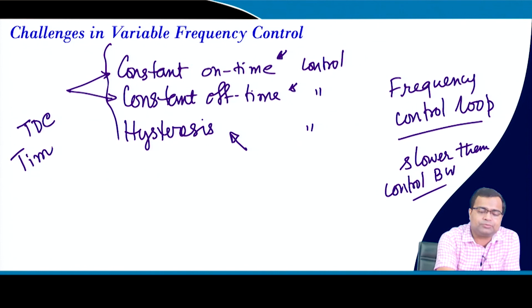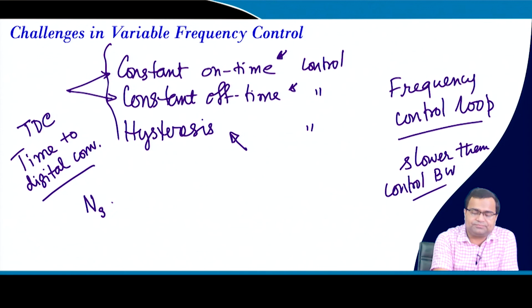And for these two techniques it is somewhat straightforward, because if you take a time to digital converter, you can get the instantaneous time period, create a feedback loop and compare it with the desired value. Let us say this is your instantaneous on time and this is your desired value. This is subtracted from the desired value, because these are all numbers, and then from the error you create a map, a function, that generates, in case of constant on time, the on time adaptation. That means it slowly adjusts the on time in order to achieve a fixed switching frequency. It can also be used to adjust the off time, or the hysteresis band.